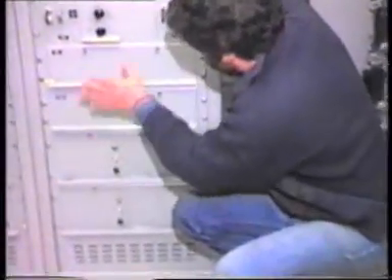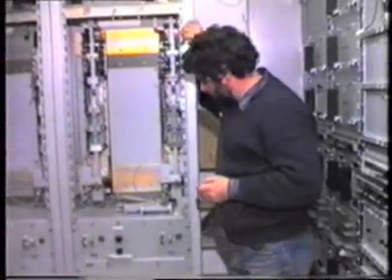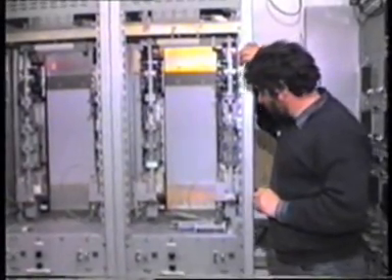The Band 2 receiver bay. Aerial distribution amplifiers top and bottom, with receivers for Radio 2, Radio 3 and Radio Scotland. And there's room for Radio 1 when that goes in. Monitoring is done using program failure monitors, so as usual there are occasional failure alarms during quiet programs. Changeover is done from an auto and a manual in a fairly standard way.